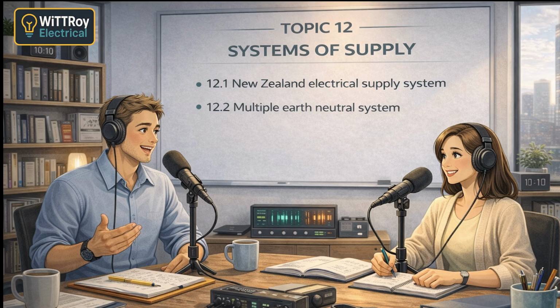Exactly. From there, transformers step the voltage up for transmission. Transmission voltages in New Zealand are typically 110 kilovolts and 220 kilovolts. Is that just to stop losses over long distances? Yep, that's the key idea. Higher voltage means lower current for the same power, which reduces heating and losses in the lines.